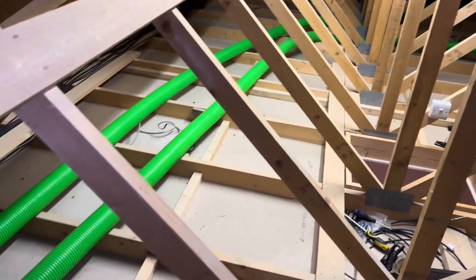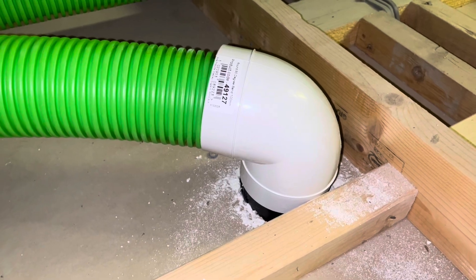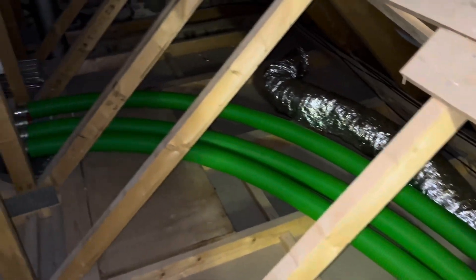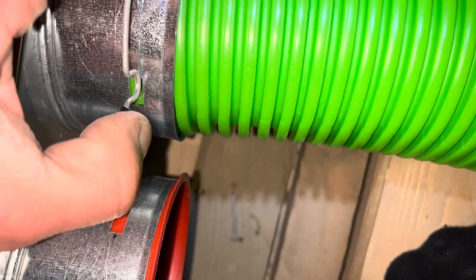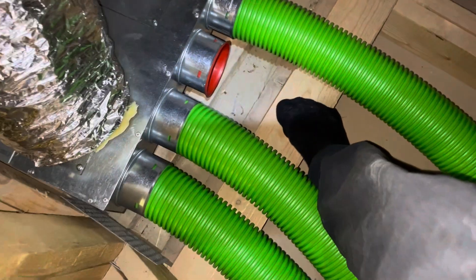It's the next morning and I've attached all the ducting in place. I'll make videos later about how I did that — for instance, how I attached the ducting to a ceiling vent. For now, it's time to attach these pipes properly to the manifolds or distribution boxes. You put the gasket here, and the other gasket two from the end, then just put it in and clip it in. That's secure — I'll do that to all the others and I'll be ready.